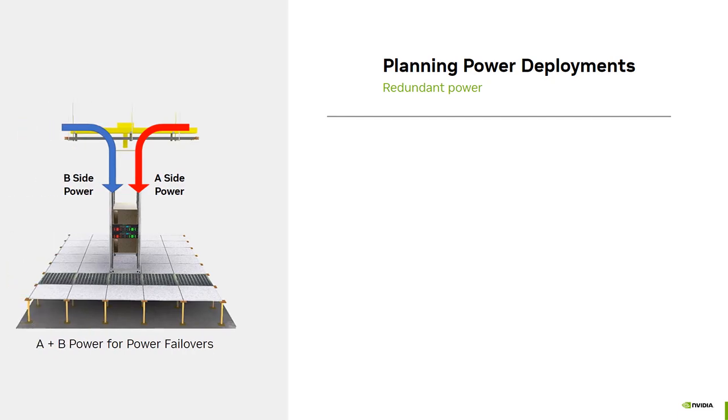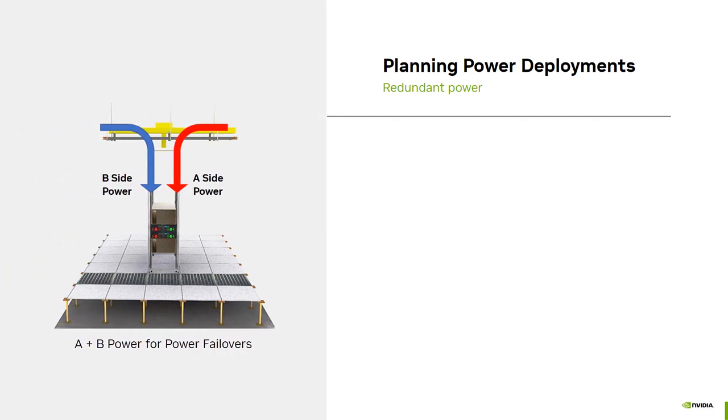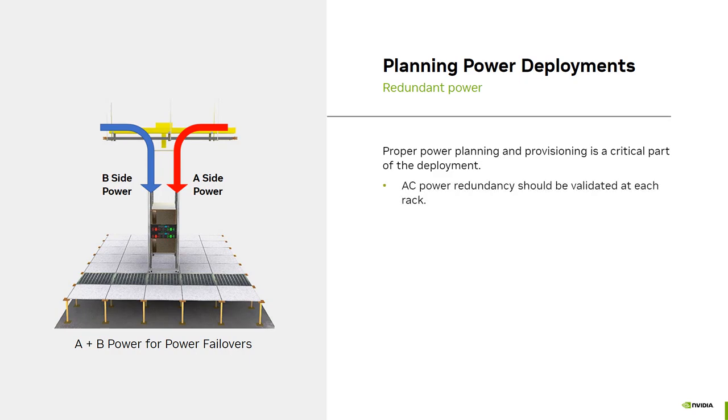Data center power provisioning must be completed prior to connecting power to the in-rack power distribution units, or PDUs, and system deployment. NVIDIA recommends that each component be supplied with redundant power sources to increase system reliability. AC power redundancy should be validated at each rack.